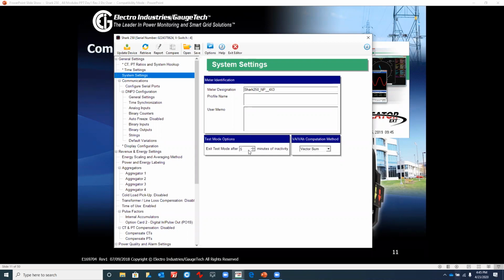And basically the test mode allows you to take a meter out of service and perform a test to check for accuracy, and we call it calibration, to make sure that the meter is within its recommended accuracy level where it should be. If it's a 0.2 meter classification, it has to test within that classification. So when you take the meter out of service, you test the meter, you inject voltage and current into the meter, and you apply it to a standard, and you make some comparisons to see how the percentage registration is, to see how far it is off.